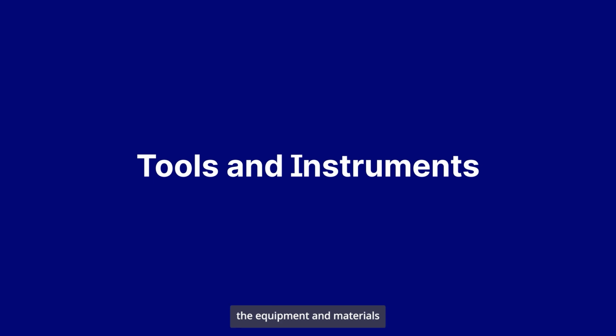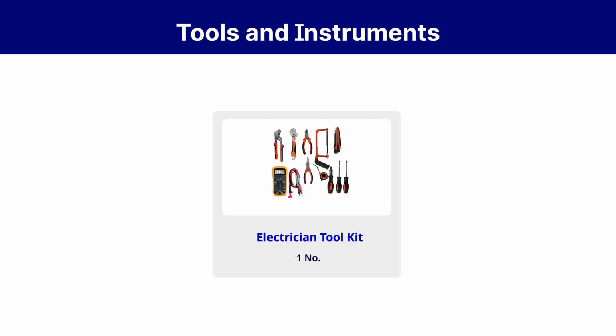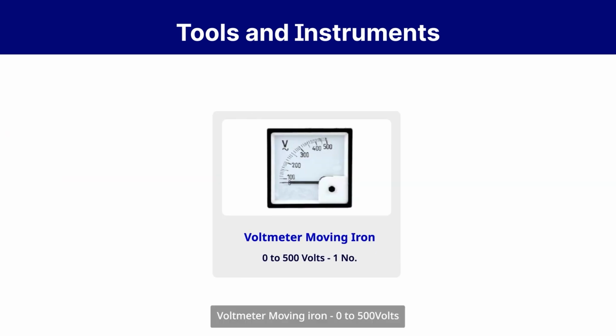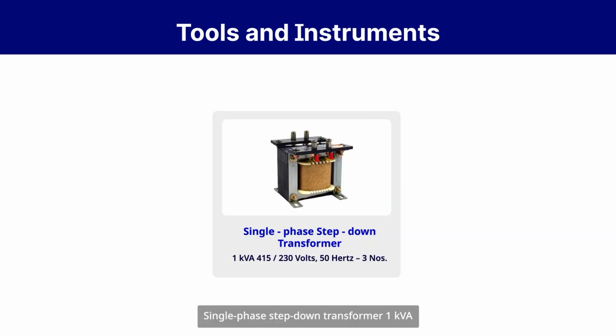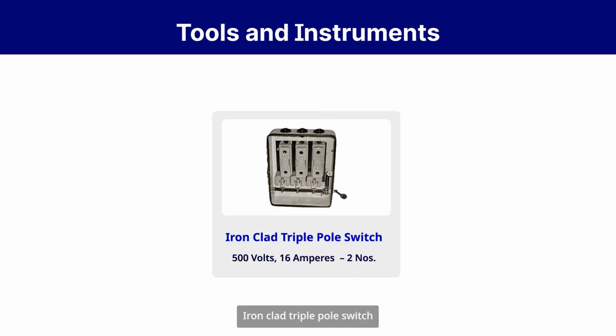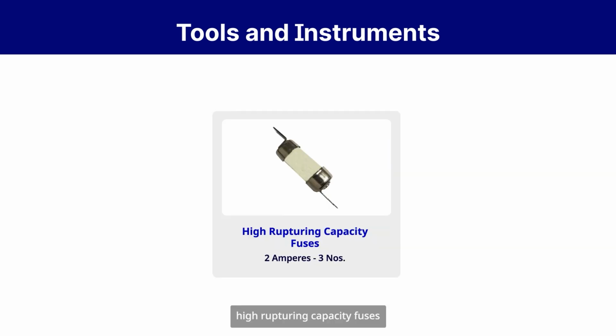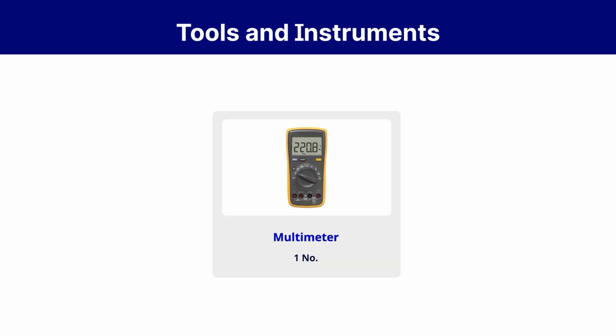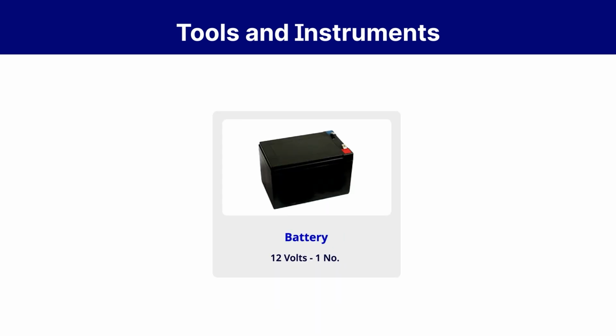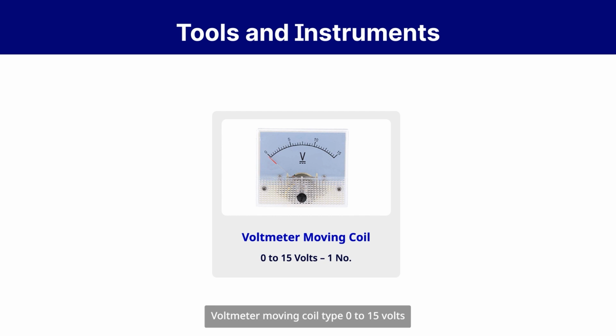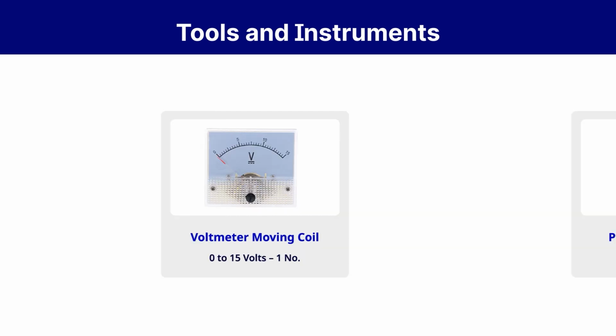Let us collect the equipment and materials to do this exercise. Electrician toolkit, voltmeter moving iron 0 to 500 volts, voltmeter moving iron 0 to 300 volts, single-phase step-down transformer 1 kVA, ironclad triple-pole switch, high rupturing capacity fuses, multimeter, battery, voltmeter moving coil type 0 to 15 volts, push-button switch.